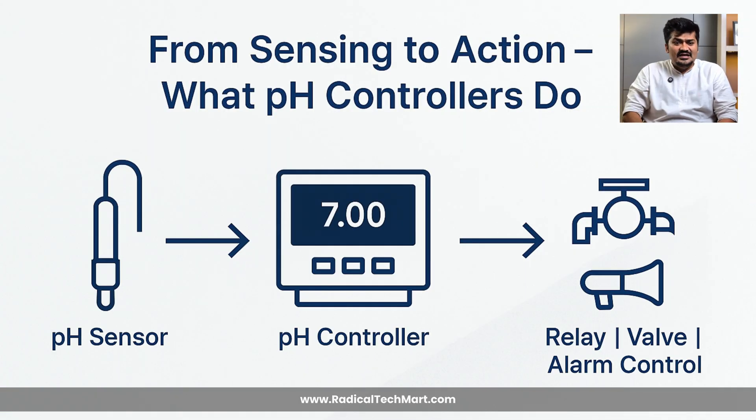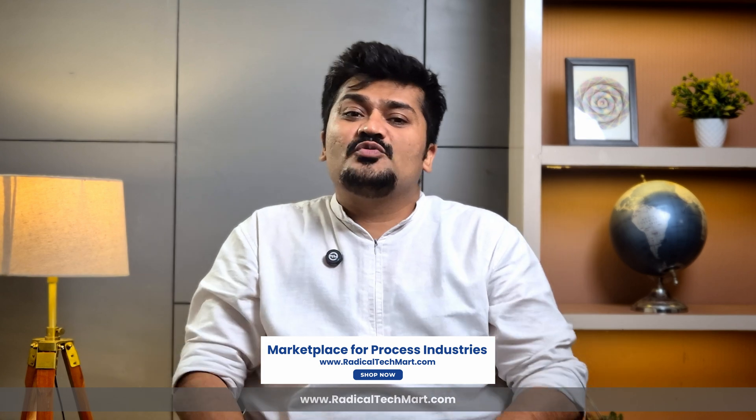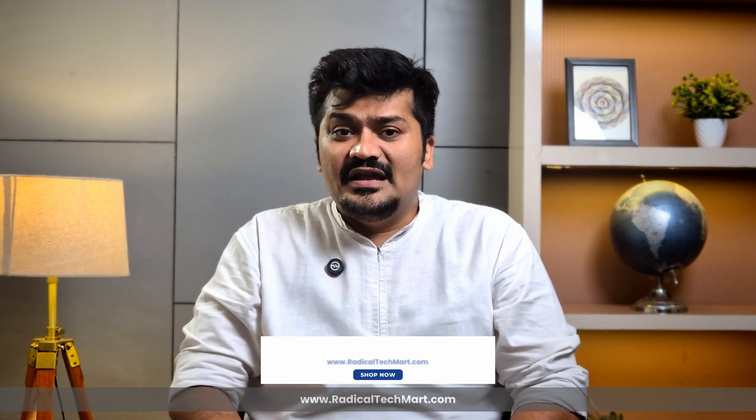Let's start with what is a pH controller. A pH controller receives the pH signal, typically in the form of a sensor or a transmitter, and then makes the decision based on a preset range or set point. It automatically turns dosing pumps on or off, opens or closes dosing valves, triggers alarms or shuts down if pH goes out of range. Unlike a transmitter that just displays the data, a controller actually controls the process.